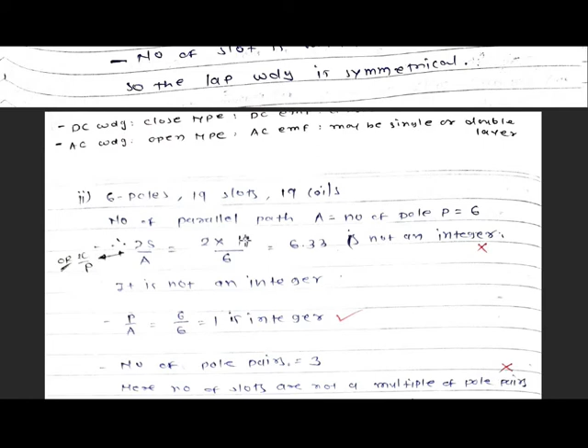Now the second problem. The example is 6 poles, 19 slots, 19 coils. So the number of parallel paths A is equal to the number of poles, which is 6. So first condition, 2C by A, sorry, 2C by P. So 2 multiplied by C, 19, divided by P, the number of poles, 6. So the answer is 6.33 and is not an integer. So our first condition is not satisfied. That's why this winding is not symmetrical.